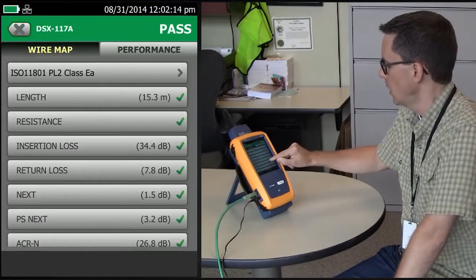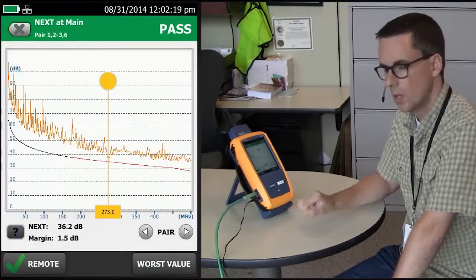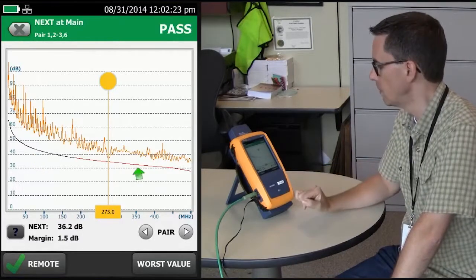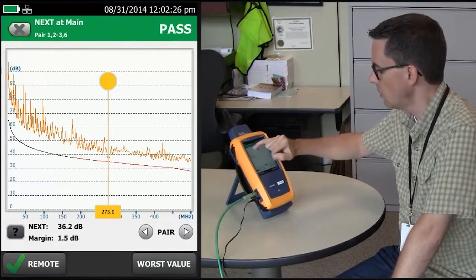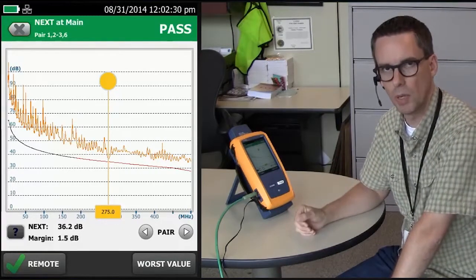When we tap on the screen here for next, we'll go to the worst performing pair. We see that part of the limit line is black and part of it is red. Where the limit line is black, any crosstalk measurement made in that region is ignored under the 4 dB rule.